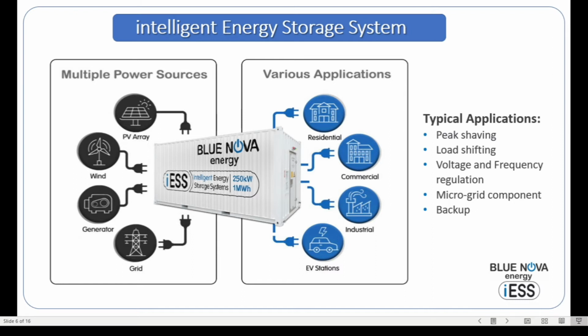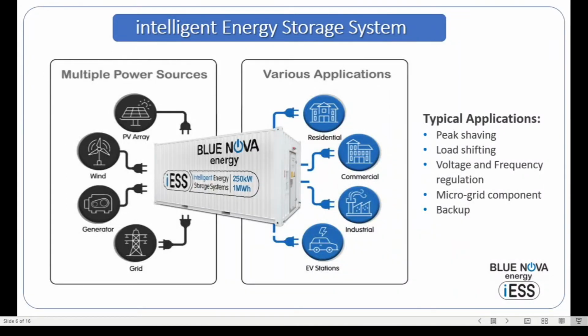Typical applications, as I've mentioned before, are peak shaving or trimming the demand, and load shifting, which means we are moving energy consumption from the off-peak or standard periods into the peak by moving energy from those cheaper areas into the more expensive areas. We can also do voltage and frequency regulation. We can do a microgrid solution, which is an off-grid application. It's one of the other videos that we did at the solar show; one can go back and have a look at that. And then finally, the system offers inherent backup capability, which allows you to use the system as a UPS system as well.